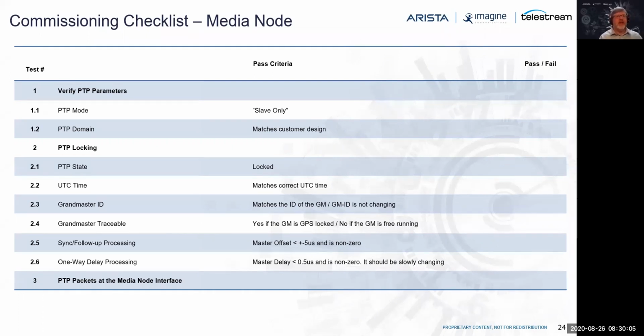For instance, some of the parameters you'll want to be checking are, does the device believe it's locked? Is it reporting the right grandmaster ID? That tells you your network has converged to the right grandmaster and is locking to the correct one. Is the one-way delay within the range that you expect? If it's showing as 0, that may not be working. Again, the actual checklist is significantly longer than this, but it's just a little sample to give you a taste.